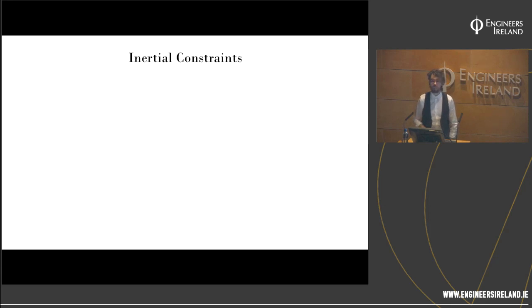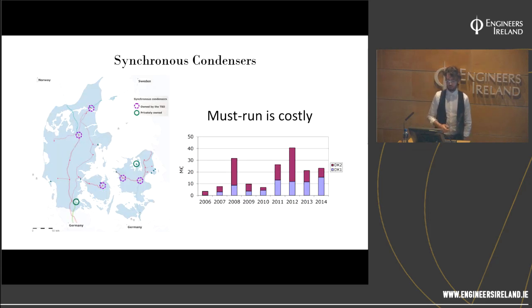Is this a role for UPS? Hmm? It's like a role for UPS. No, because a synchronous condenser is a synchronous machine, so it has rotating mass, and it's not only that, the source of energy, you could argue, doesn't matter, but it's directly coupled to the grid frequency. So when the frequency falls, it will inherently inject its stored energy to the grid. Well, it'll slow down, and because it slows down, it injects its stored energy. The thing with a UPS is like synthetic control of a wind turbine, in that it's not directly coupled to the grid. I'll get on to that in a sec.